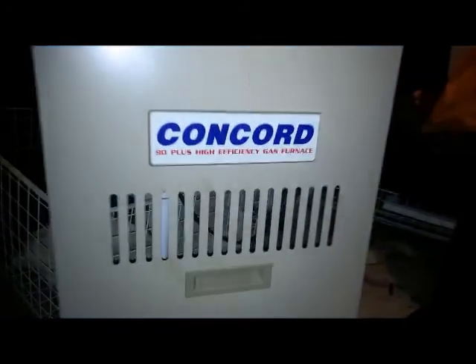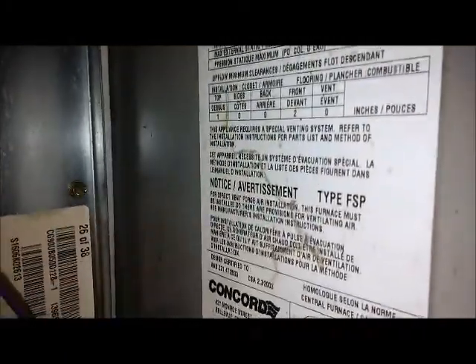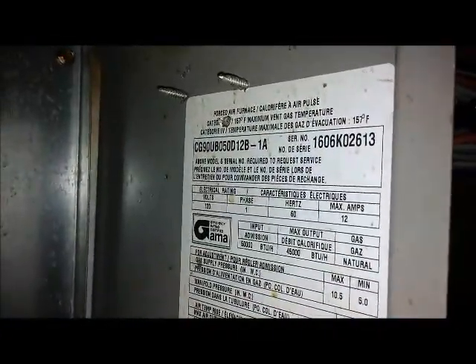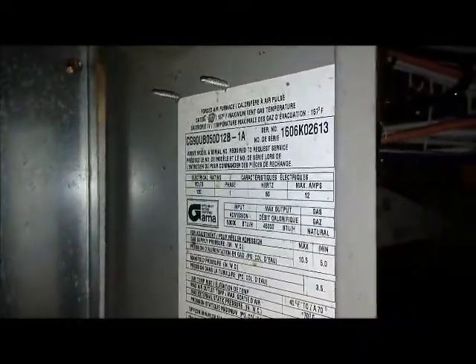Hold up on this furnace here, the 90 plus — Concord, not sure, it looks like a Nordyne. Anyway, it's a model and serial number. We were getting a 7 flash when I showed up here, which is telling us: 7 flash lockout due to no ignition.